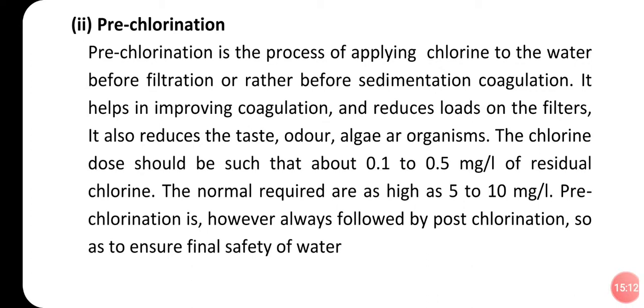And after all those things, the residual chlorine or free chlorine will be available. That chlorine must be 0.1 to 0.5 milligram per liter. Do you understand? It is not the dose actually. The dose must be such that after reaction 0.1 to 0.5 milligram per liter is available in the water.